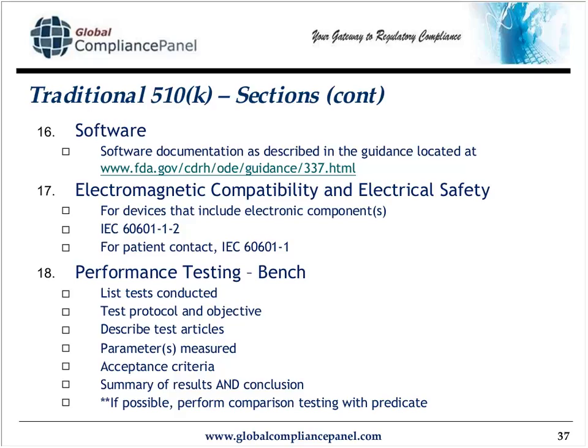If you can get a predicate device, if it's yours, you certainly can. If it's your customer's, sometimes you can use maybe a friend of your company that you can fund to buy a handful of the competitor devices, the predicate devices. The reviewers really like it when you perform comparative testing, comparative performance testing between your device and the predicate device.